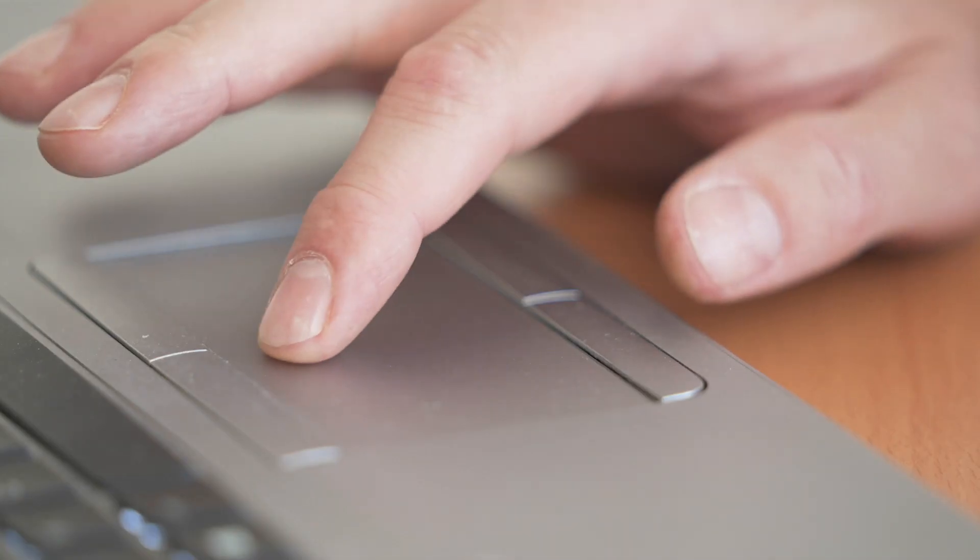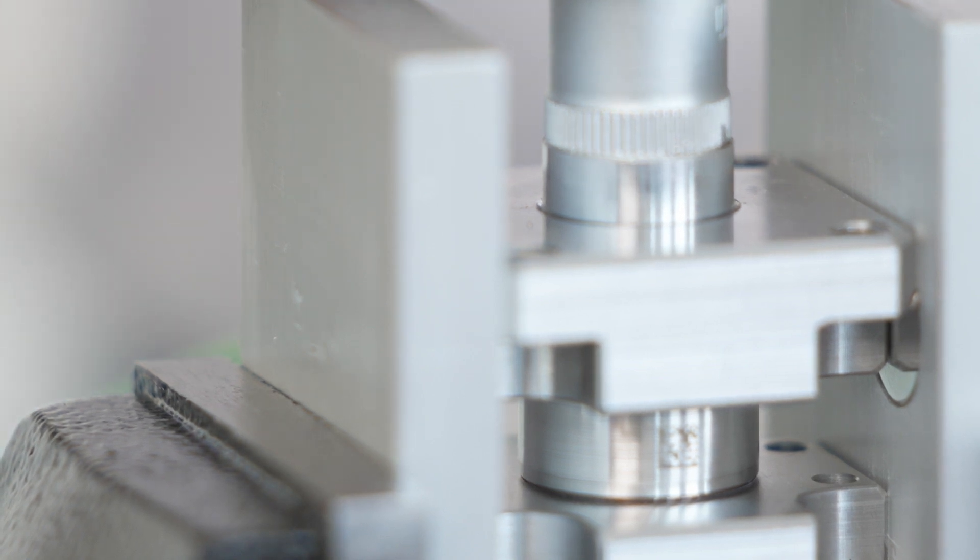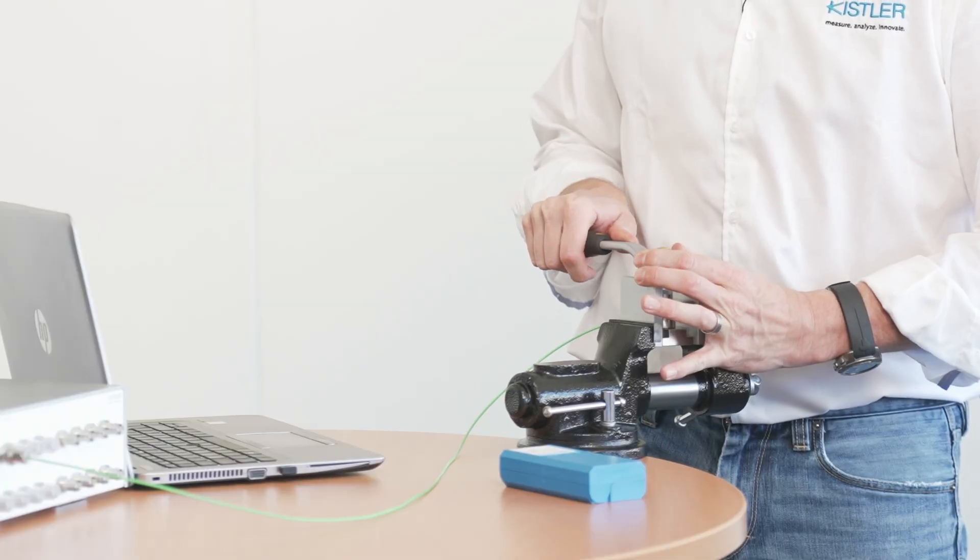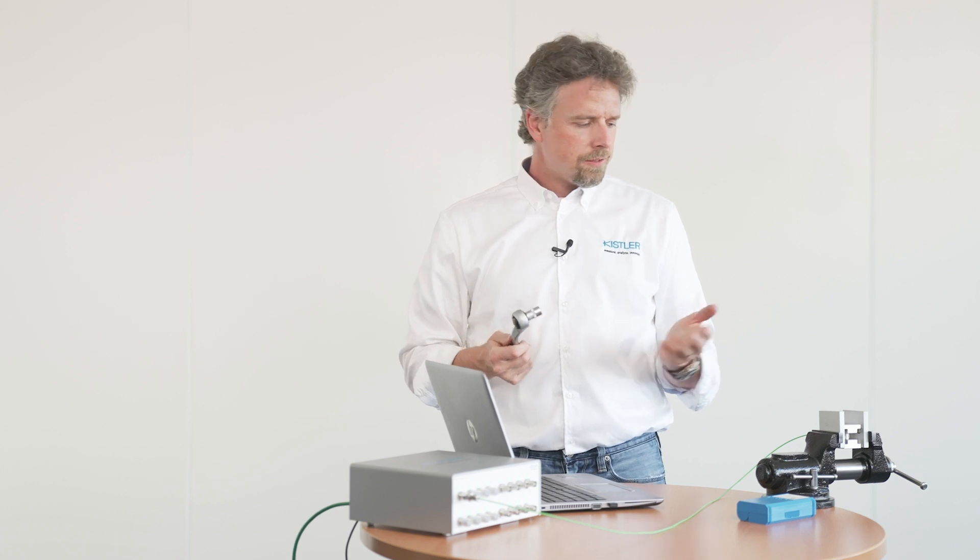I start measuring here on our software. And we apply the recommended 20% of the nominal force, which is in this case 7 kilonewtons. Okay, that's it. Your sensor is preloaded and ready to measure.